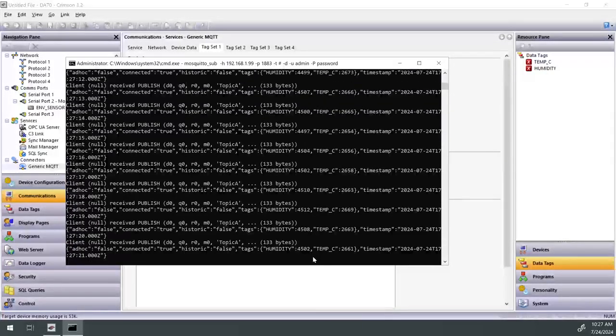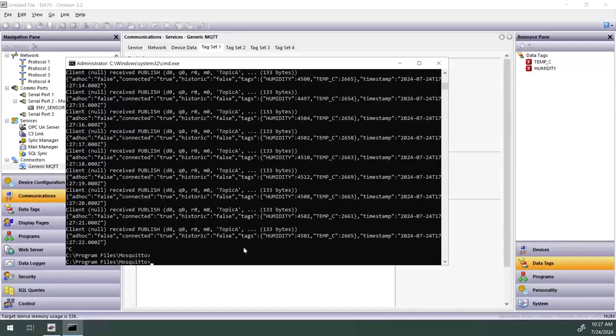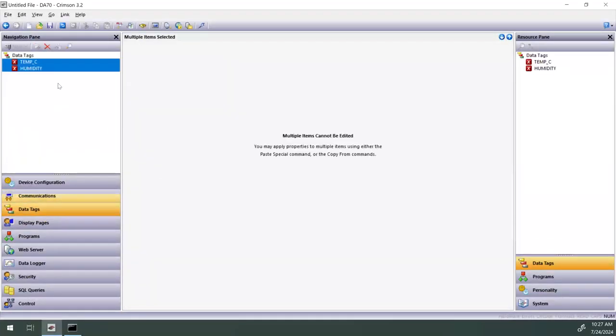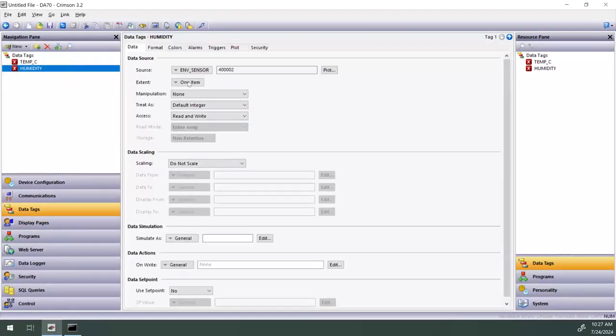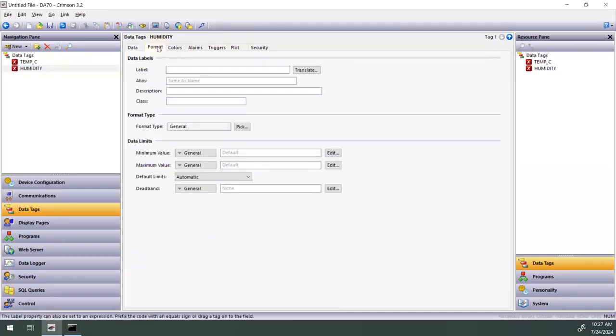So this is where deadband comes into play. Just real quickly, I will jump to my humidity tag, and we will put a deadband on that tag. So instead of every time it changes by 1, I'll say this has to change by at least 10 in order to transmit a change.